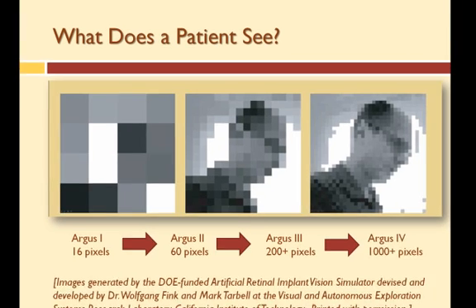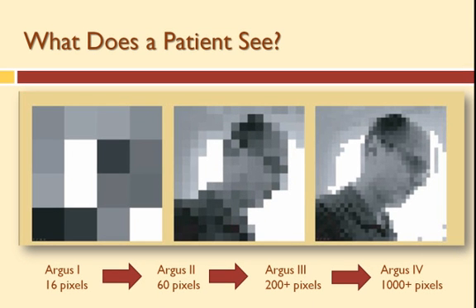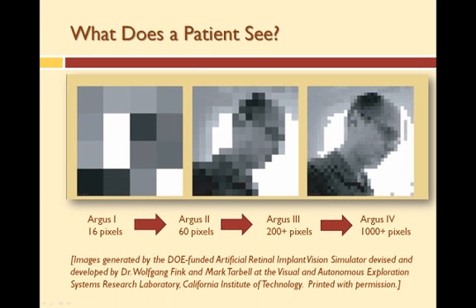Increasing the number of electrodes in the retina array results in more visual perceptions and higher resolution vision. In the Argus 1, there were 16 electrodes, or 16 pixels, and it took patients about 15 seconds to recognize objects. In the Argus 2, there are 60 pixels, and processing time was brought down to 2 to 3 seconds — enough resolution to see the edges of doors or the shape of a building. Argus 3 is being designed with more than 200 pixels, and Argus 4 is anticipated to have at least 1,000 pixels. The hope is that with 1,000 pixels, one might actually have facial recognition.